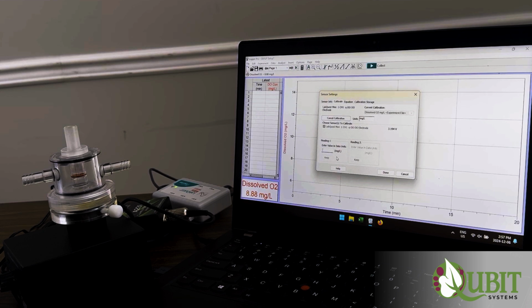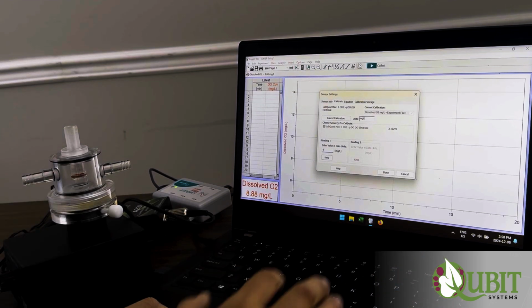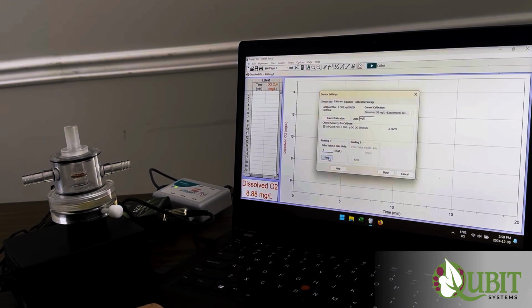And you can get that number from a local weather station, which is about 101 kilopascals or 760 millimeters of mercury. And in your manual, you will find a table which will provide you with the values for expected dissolved oxygen levels in milligrams per liter at a given temperature and pressure. In this case, it's 9 milligrams per liter in air saturated water at these conditions. We click keep on that first reading, and then we proceed to reading 2.